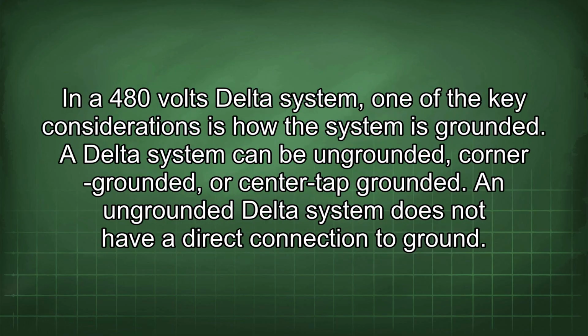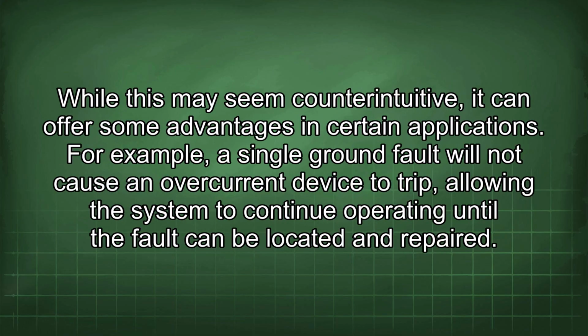In a 480 volts delta system, one of the key considerations is how the system is grounded. A delta system can be ungrounded, corner grounded, or center tap grounded. An ungrounded delta system does not have a direct connection to ground. While this may seem counterintuitive, it can offer some advantages in certain applications.